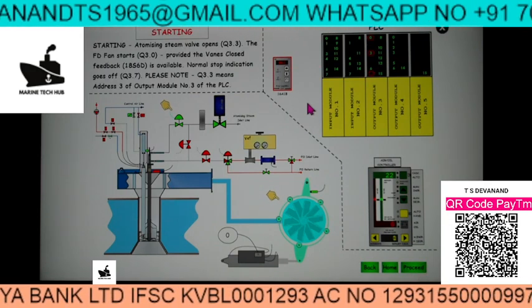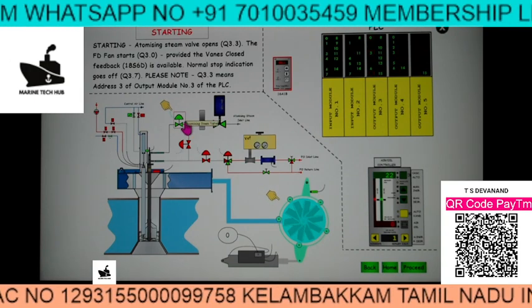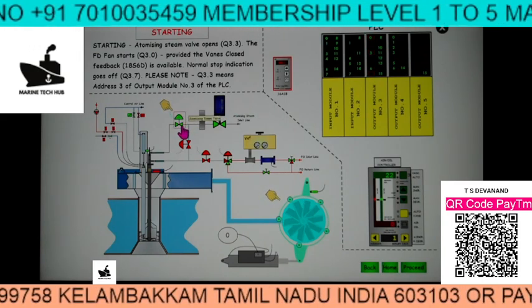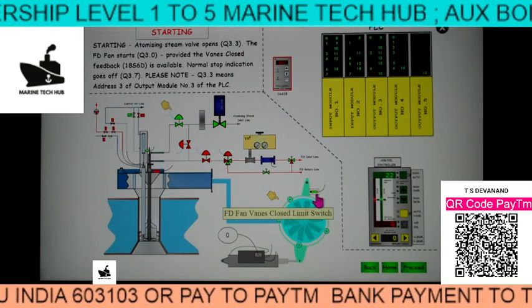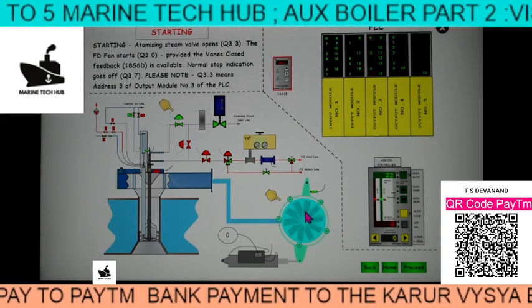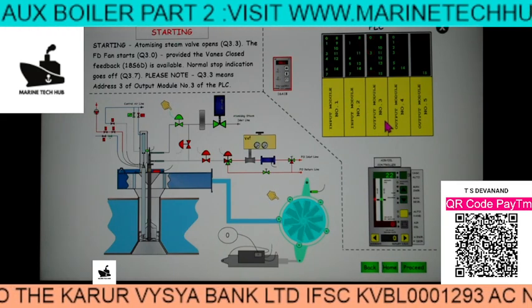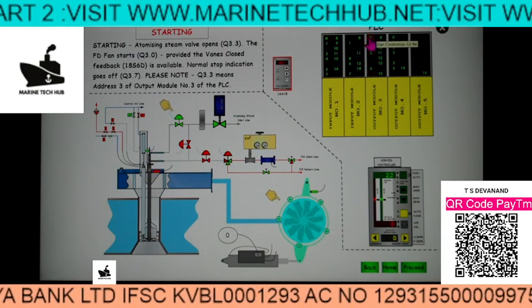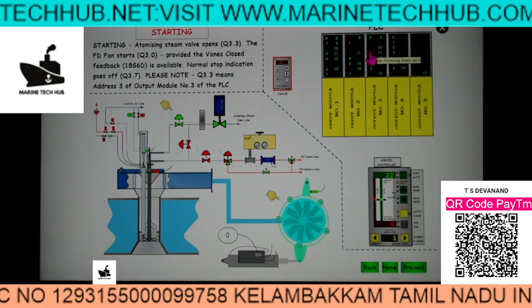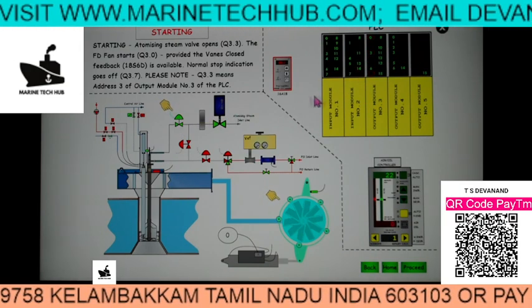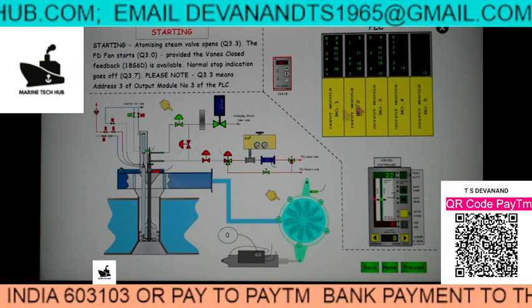The second thing is the signal going for the atomizing steam valve — the atomizing steam valve needs to be open. You can see it is green, meaning it is open. The FD fan also needs to be started. Initially the interlock should be there, otherwise it will not open, because if it is in the open condition it will draw a huge current. You can see in PLC module 3: the first one says 'start combustion FD fan,' and 3.3 is 'open atomizing steam valve.' The last one shows burner normal stop conditions — right now it is in the stop condition.